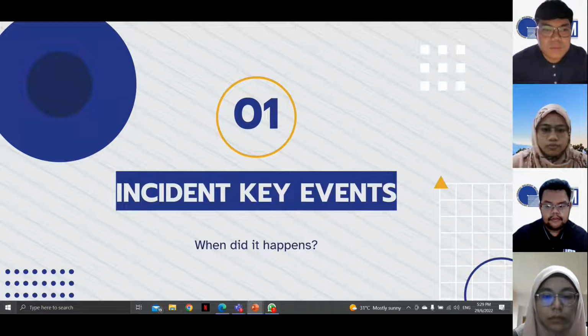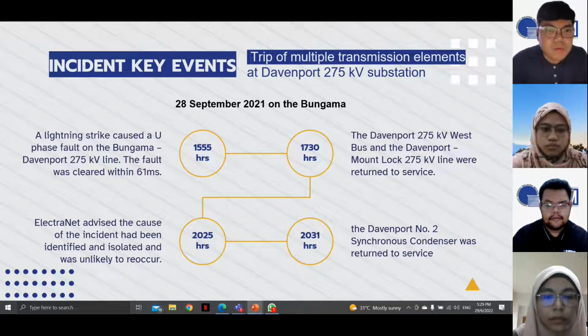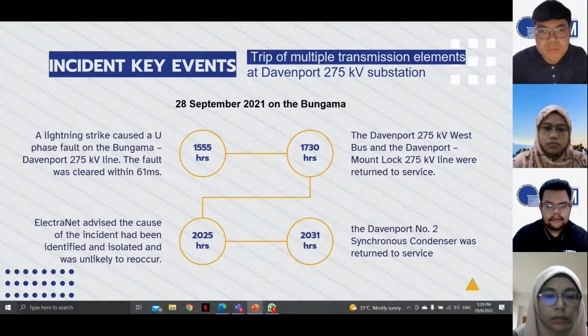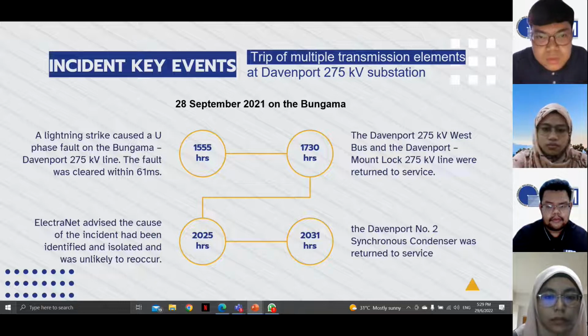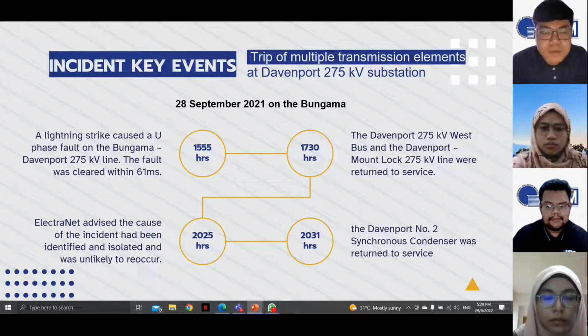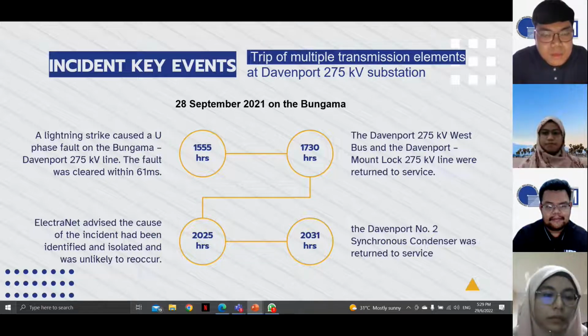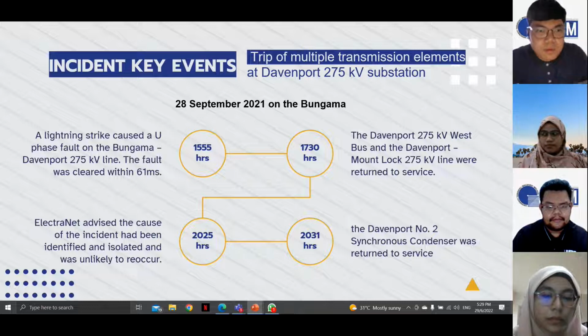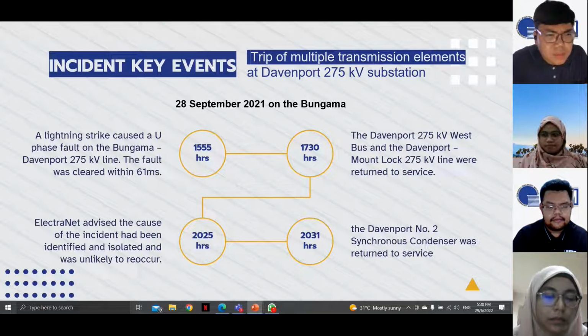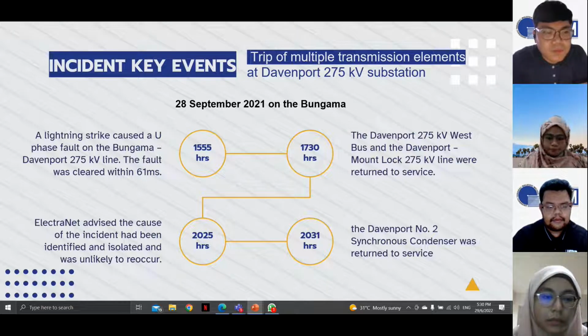For the first part, we'll explain a bit about the incident key events, which is when did it happen. First of all, this incident, the trip of multiple transmission elements, happened at the Davenport 275 kV substation. The date of this incident is the 28th of September 2021, at 3:55 p.m. A lightning strike caused a U phase fault on the Bungama Davenport 275 kV line, and this fault was cleared within 61 milliseconds.